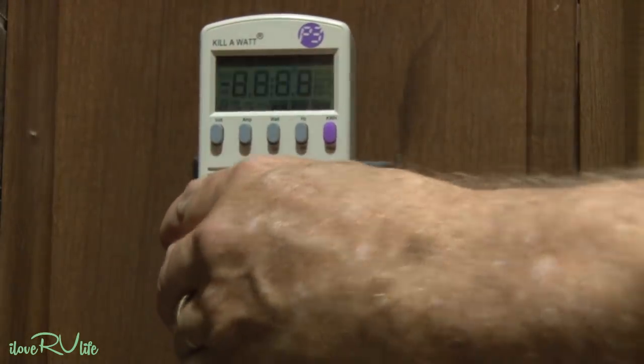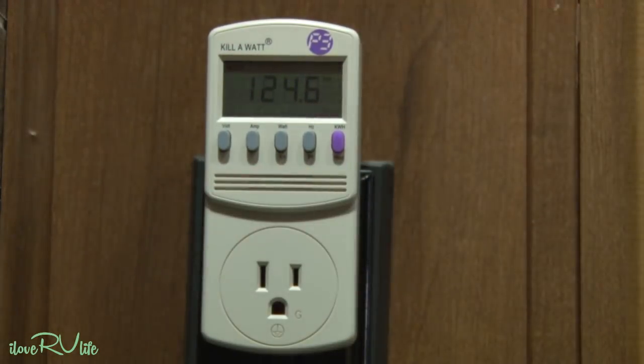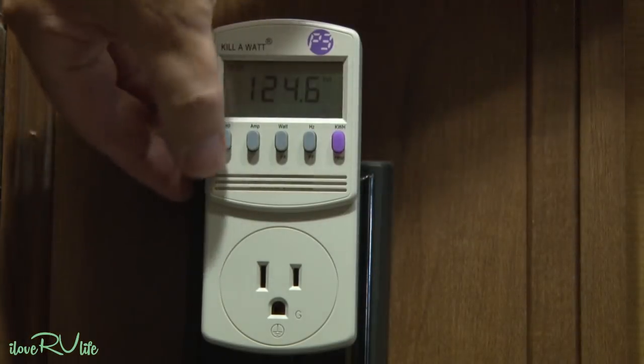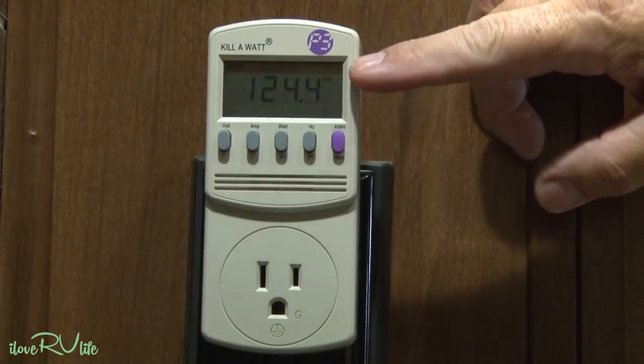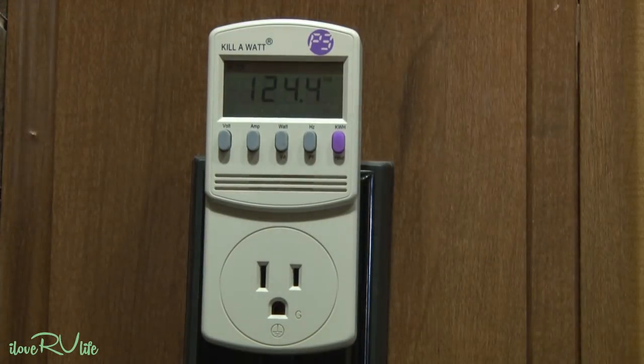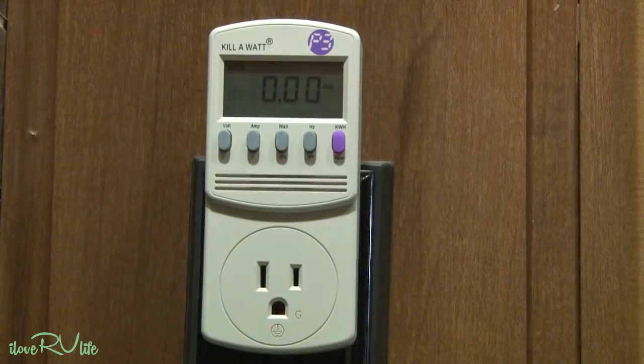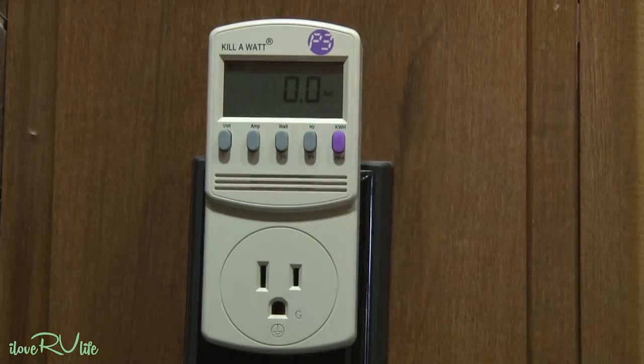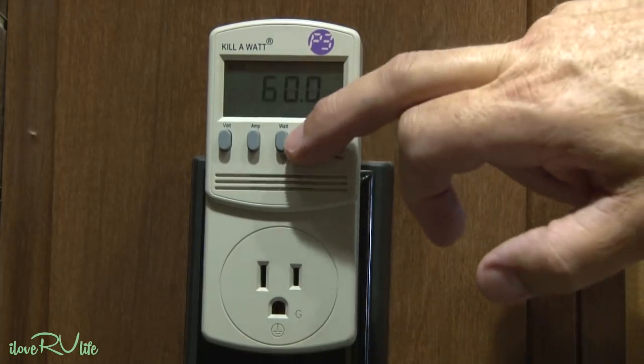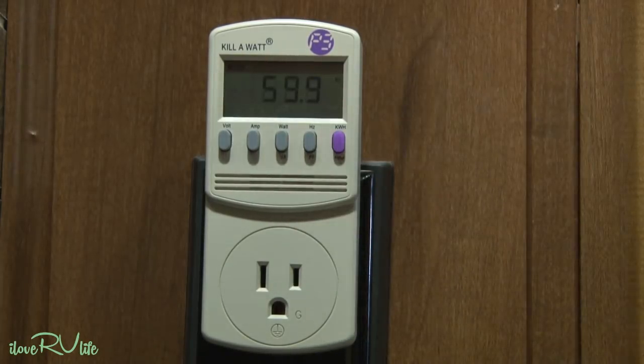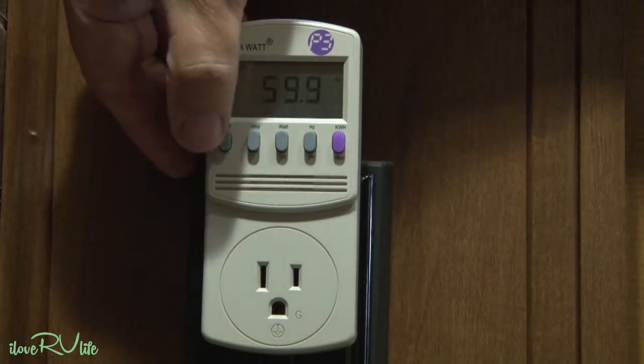I'm going to take the Kill A Watt meter and plug it into my AC outlet. Immediately, based on the button I have pressed for voltage, you see I've got 124.4 volts. There should be no amperage or watts being used right now, and you see I've got a good 59.9, basically 60 cycles coming in. That's all good stuff - that's exactly what we want to see happening outside of one of these meters.